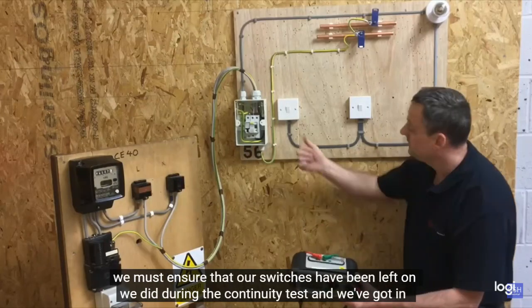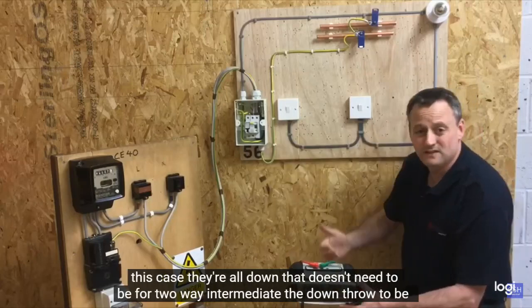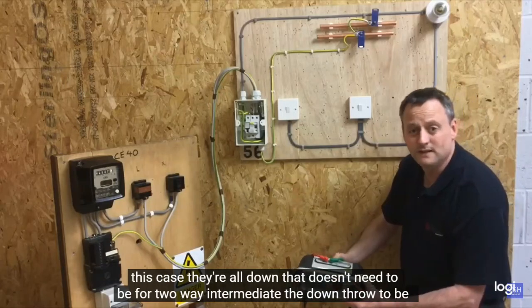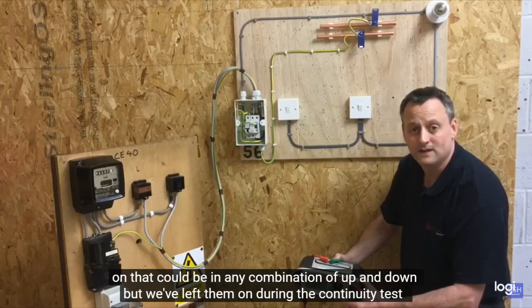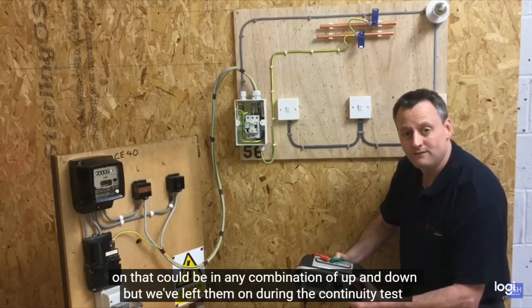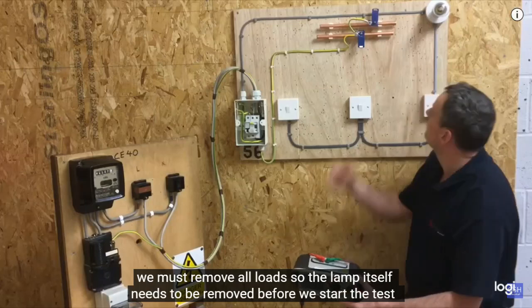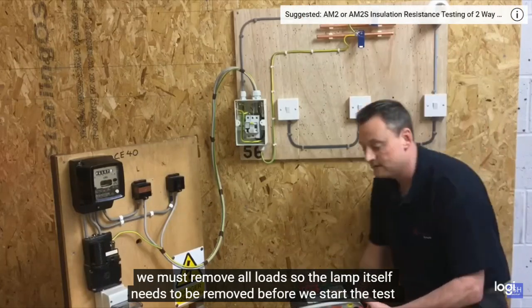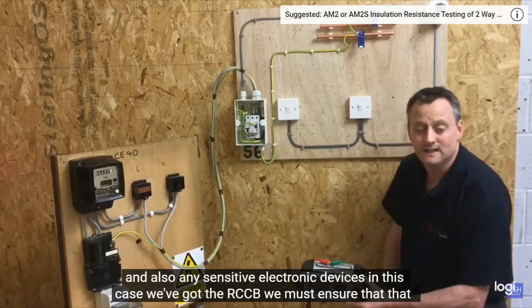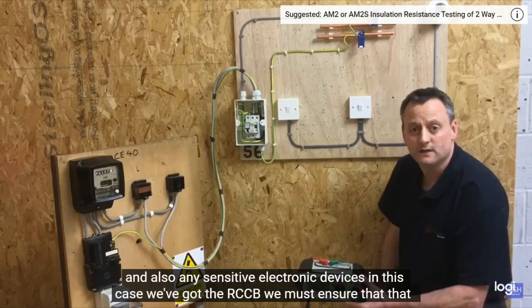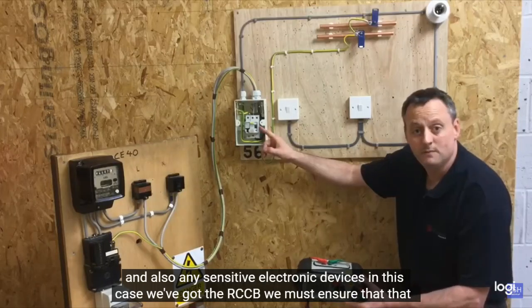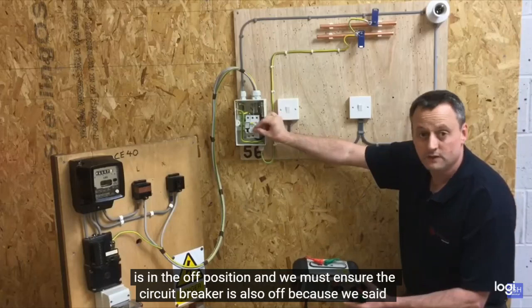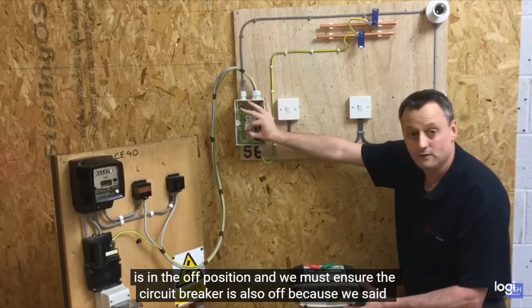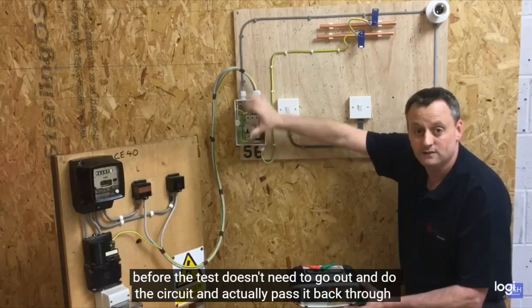We must remove all loads, so the lamp itself needs to be removed before we start the test, and also these sensitive electronic devices. In this case, we've got the RCCB. We must ensure that it is in the off position, and we must ensure the circuit breaker is also off, because as we said before, the test doesn't need to go out and do the circuit once you pass it back through the circuit breaker and across the bottom of the RCCB. So the supply is isolated, we're ready for the insulation resistance test.